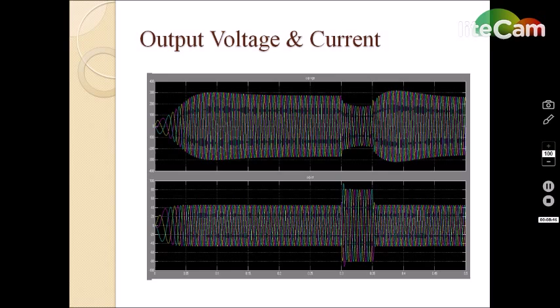You know that when there is no fault, the reactive power will be 0. When a fault occurs, this generator will give you reactive power. This is one of the advantages of the permanent magnet synchronous generator: when a fault occurs, the generator itself can generate the reactive power support required by the system. So these figures clearly show what changes and disturbances occurred in the voltage and power generators when a three-phase fault occurred.